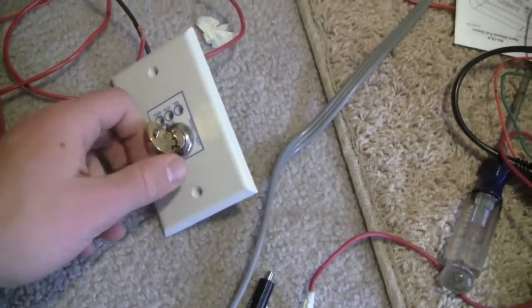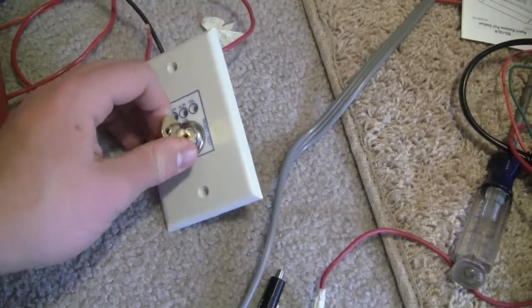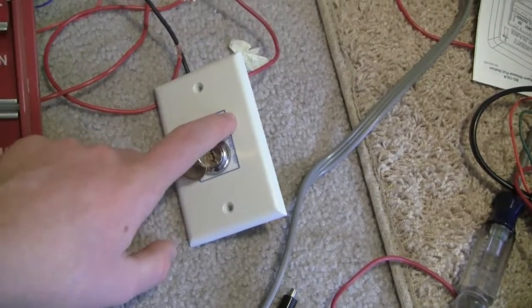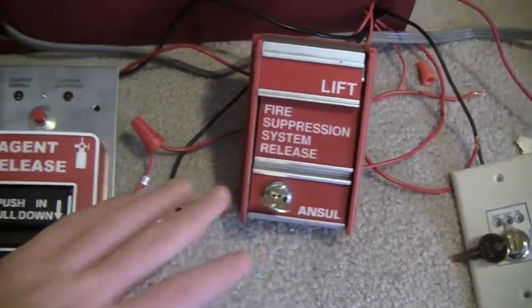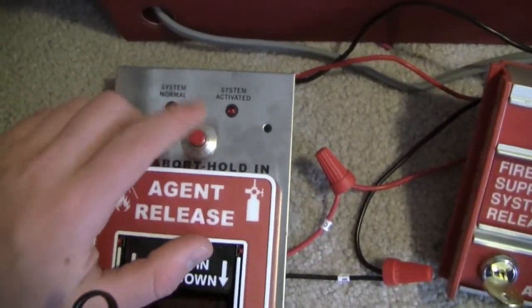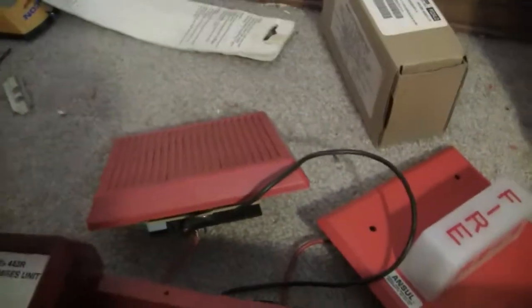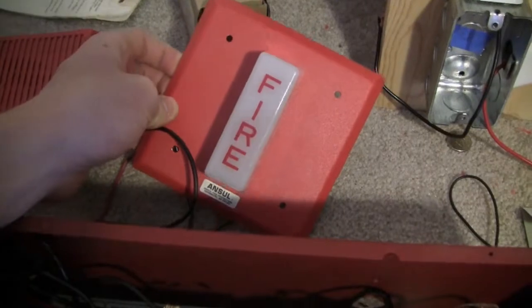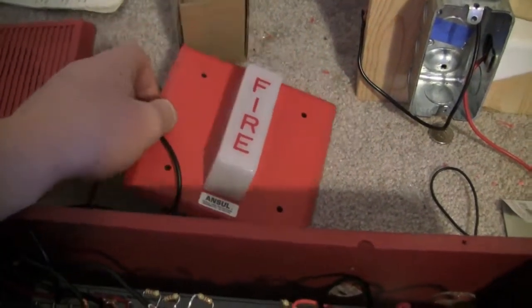Right here I have an EST key switch that I'm using, and this key switch is hooked up to the Manual Release Zone. One of these is hooked up to Zone 1, one is hooked up to Zone 2, and the Abort Button is hooked up to the Abort Zone. Up here for the alarms I have a Wheelock MT Horn set on low volume bell, and an Ansul strobe — this one's actually made by Wheelock, just branded by Ansul.